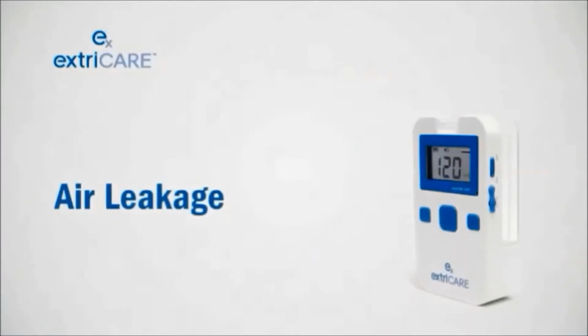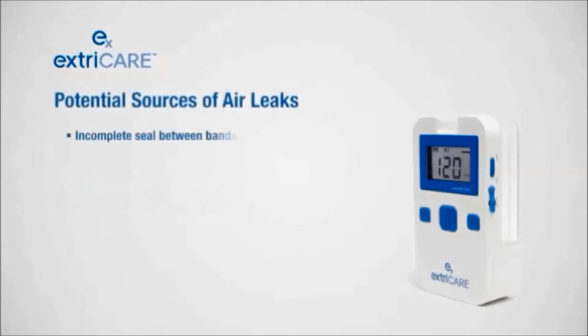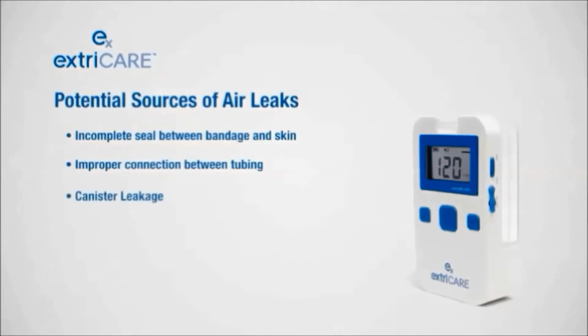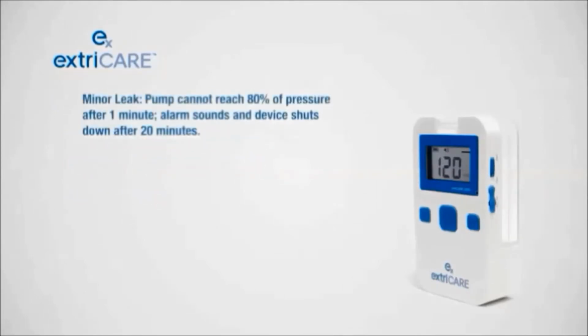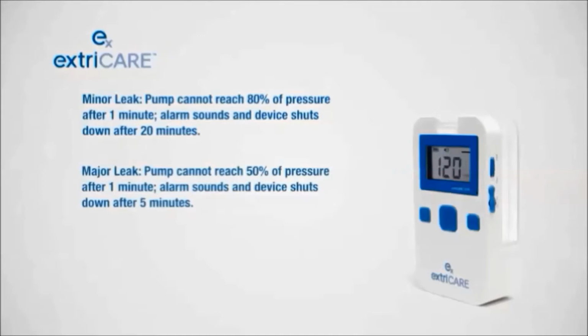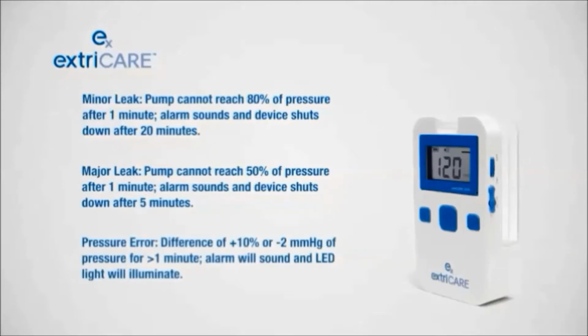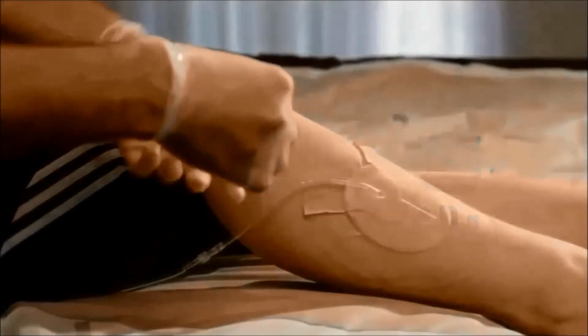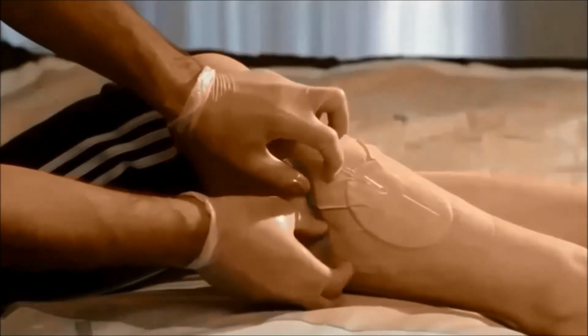There are various potential sources of air leaks, including an incomplete seal between bandage and skin, improper connection between tubing, and/or canister leakage. For minor leaks, an alarm will sound and the system will shut down after 20 minutes. For major leaks, an alarm will sound and the system will shut down after 5 minutes. For pressure errors, if there is a difference of plus 10% or minus 2 millimeters of mercury for more than 1 minute, an alarm will sound and the LED light will illuminate. This is a small leak, but the pump will continue to run. For any of these errors, find the point of leakage and create the proper seal.